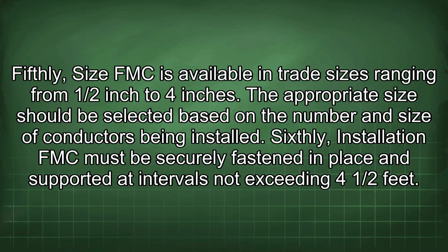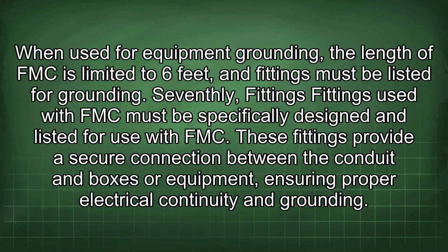Fifthly, size. FMC is available in trade sizes ranging from 1/2 inch to 4 inches. The appropriate size should be selected based on the number and size of conductors being installed. Sixthly, installation. FMC must be securely fastened in place and supported at intervals not exceeding 4 1/2 feet. When used for equipment grounding, the length of FMC is limited to 6 feet, and fittings must be listed for grounding. Seventhly, fittings. Fittings used with FMC must be specifically designed and listed for use with FMC. These fittings provide a secure connection between the conduit and boxes or equipment, ensuring proper electrical continuity and grounding.